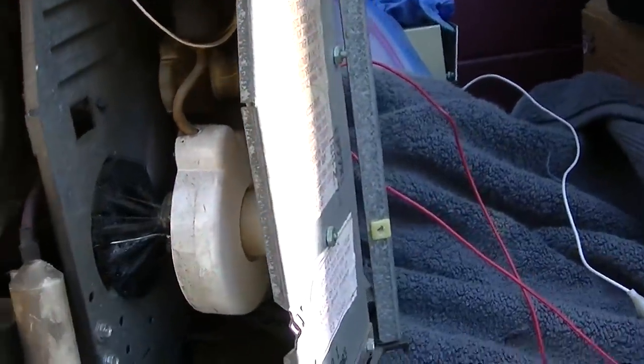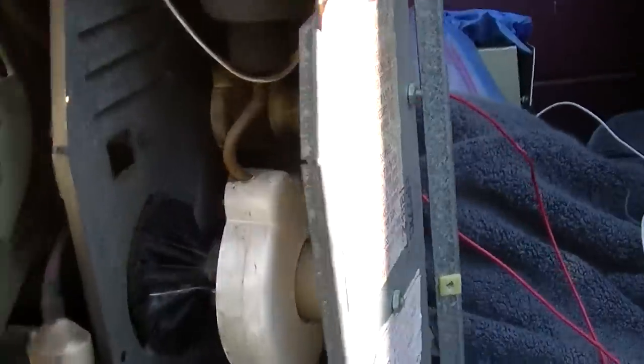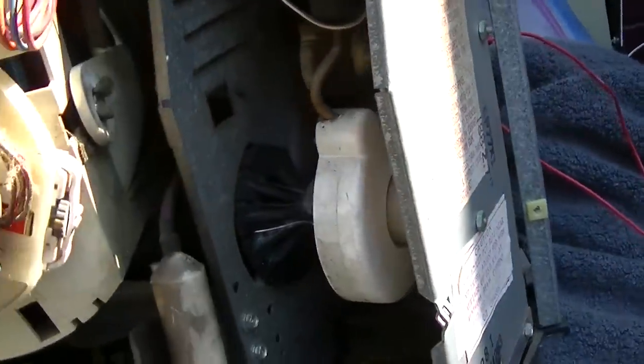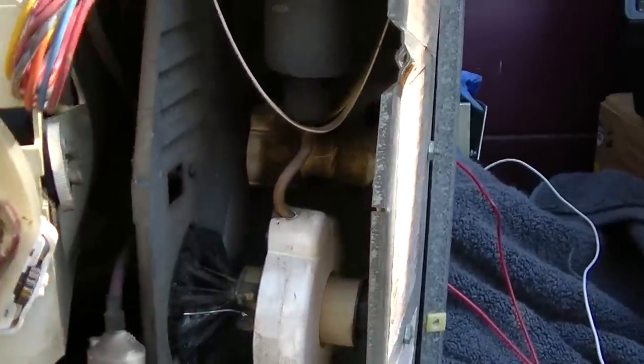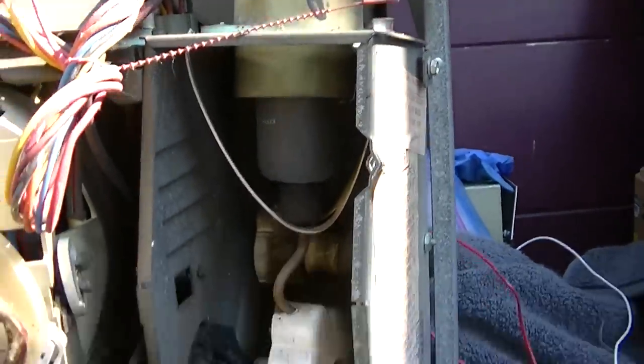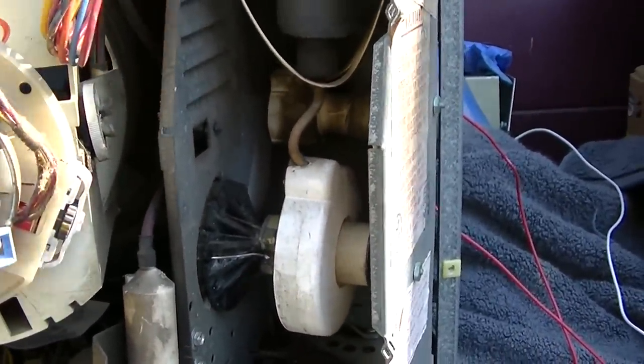I believe these General Electrics are designed so you just change this part. See how the core is bolted to the can? So you could just, I don't know how you get it apart, but I don't think you change that thing up there. Maybe the can comes into pieces, and then you just replace this donut here. You don't change the whole core on these GEs.